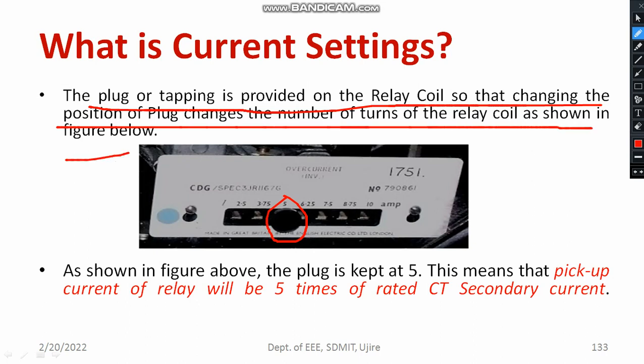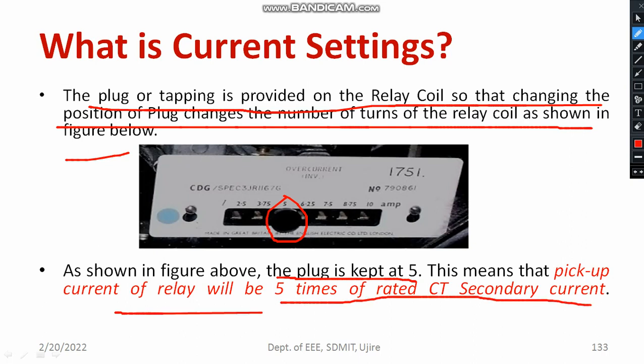Now, we have chosen PS equal to 5. The plug is kept at 5. That means the pickup current of the relay will be 5 times the rated CT secondary current — that is the meaning. So here, plug setting will be taken as 5. This you need to keep in mind.